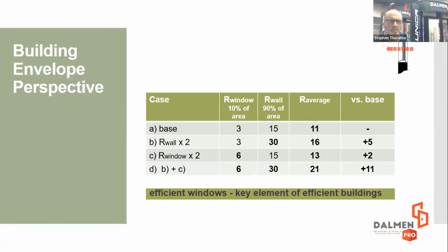A lot of houses in Ottawa might have at least Low-E windows if they came from the 80s or later, so R3 might be a reasonable number to pick for the windows. If you've got 2x6 walls, including the framing, R15 might be reasonable. If it's an older house, before the 80s, this would be a little high. But if you have R3 for 10% of your wall area and R15 for 90%, on average your wall area is around R11.